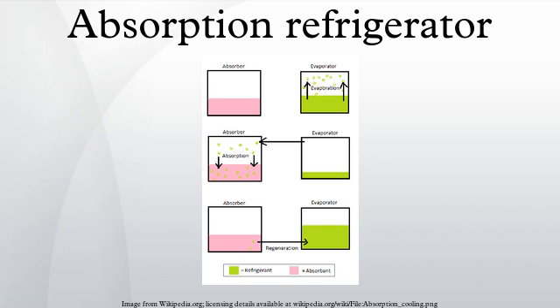An absorption refrigerator changes the gas back into a liquid using a method that needs only heat and has no moving parts other than the refrigerant itself. The absorption cooling cycle can be described in three phases. Evaporation: A liquid refrigerant evaporates in a low partial pressure environment, thus extracting heat from its surroundings. Due to the low pressure, the temperature needed for evaporation is also lower.